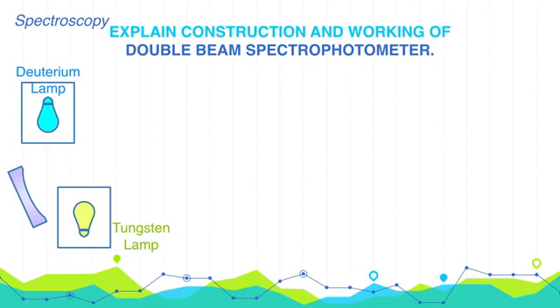UV light can be obtained by heating the filament which is filled with either hydrogen gas or deuterium. Visible radiation can be obtained by incandescent lamp with tungsten filament, and IR radiations can be obtained by heating Nernst Glower at the temperature of 1500 to 2000 degrees Celsius.